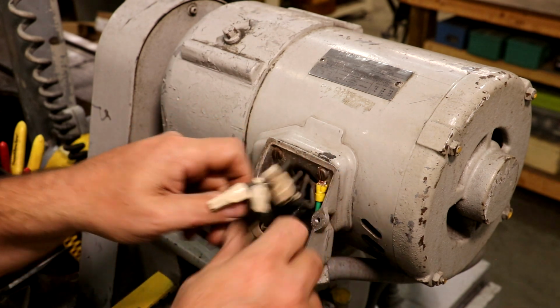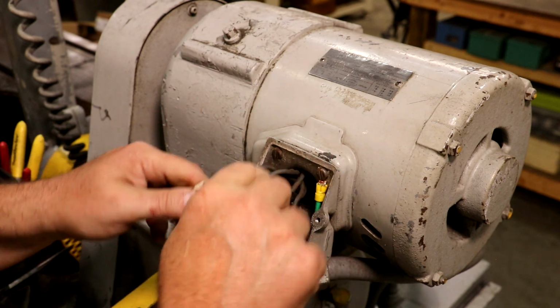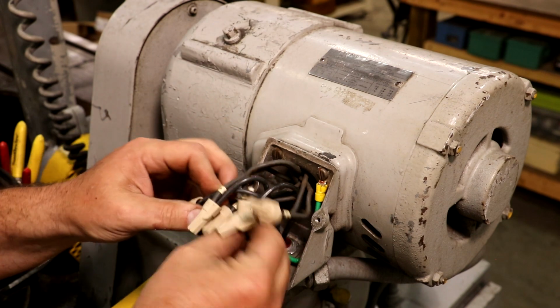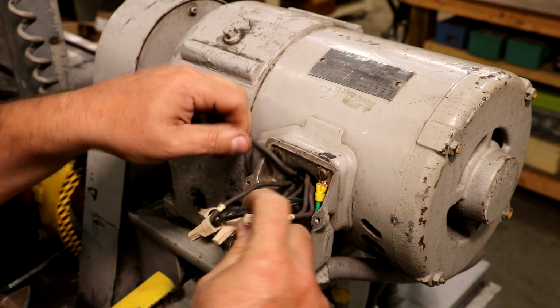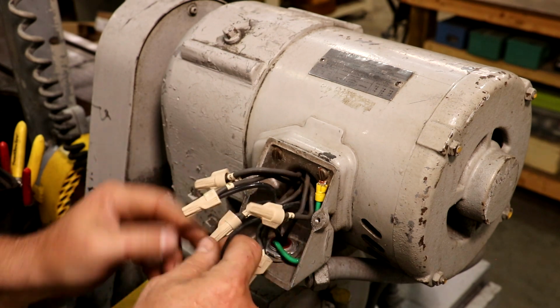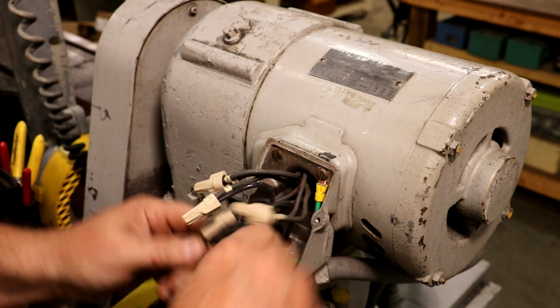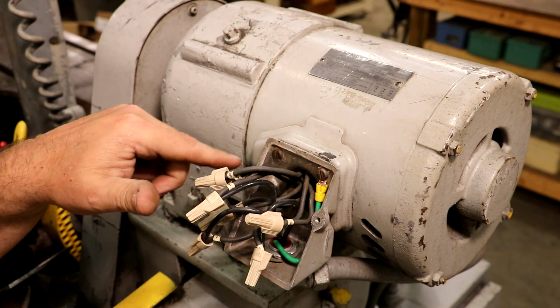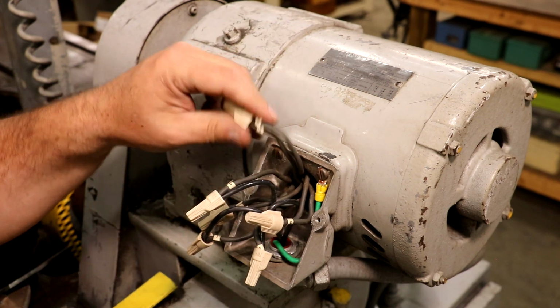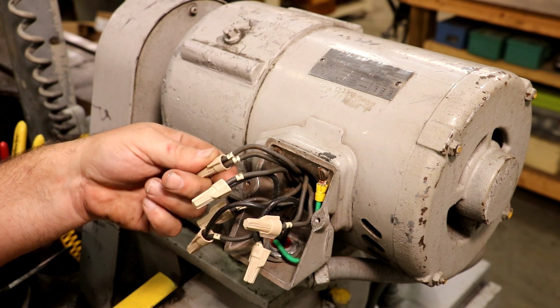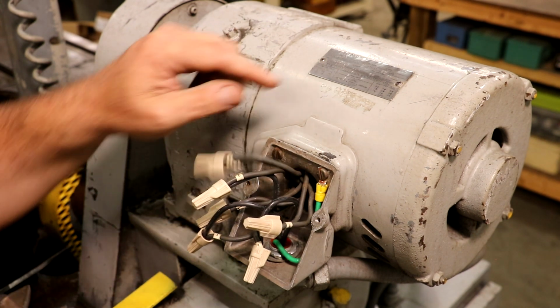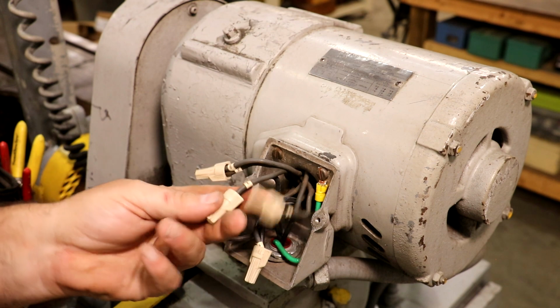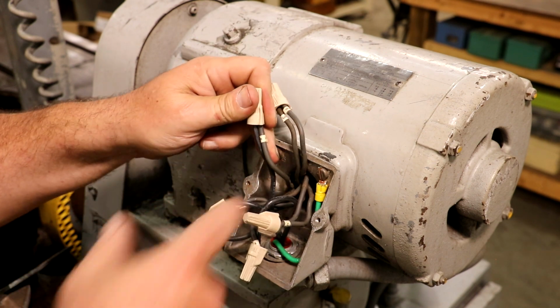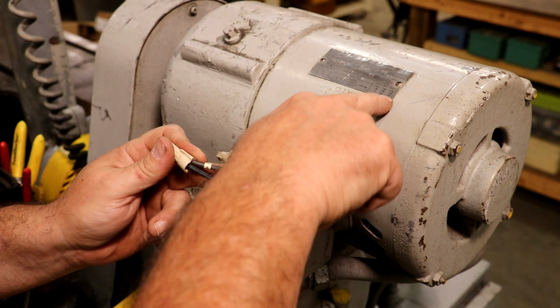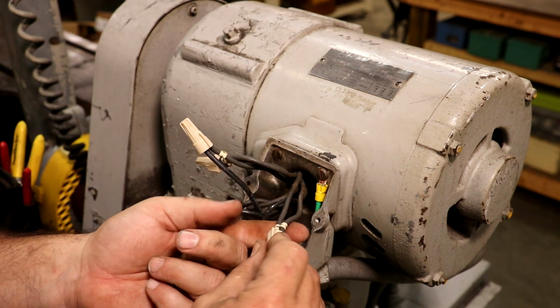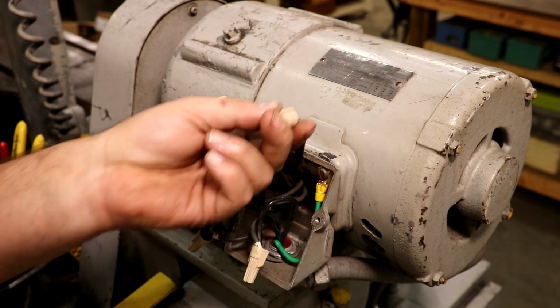And I'm going to just pull all these out and confirm that it is indeed wired for the high voltage, and I can already tell it is because there's only 2 wires on each lead, which matches what's up here. On the low voltage, one set's going to have 3 wires in it, but if you look here, we have 6 and 9 tied together, and I look here, 6 and 9 are tied together. This one is 3 and going to one of our inputs. 3 goes to the line. 5 and 8 are tied together. There's 5 and 8 tied together.